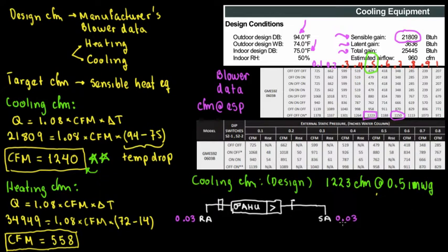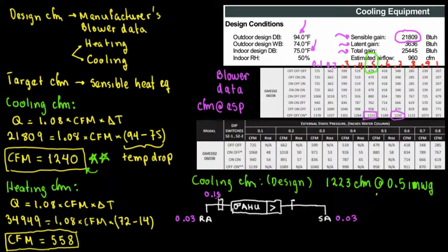The filter can be up to 0.15 inches — sometimes 0.10 for a lower MERV filter. The more the MERV rating, the higher the pressure loss. So you might not be able to upgrade to a higher MERV filter because it increases resistance. The balancing damper contributes about 0.03 inches, and the coil — depending on manufacturer tables — adds about 0.17 inches.